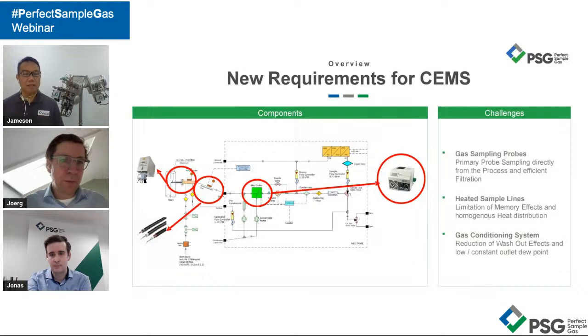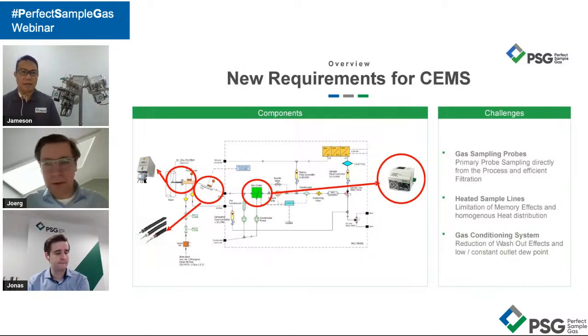Would you agree that we really try to point out here the very main components, right? Yeah. In fact, the three main components of the sampling system start with the sample probe. This is all the way up there, and we must get it right. And after the probe, it is so critical that after removing the particles, we clean up the particles, and then we have to address the dew point. We want to maintain the sample as representative.